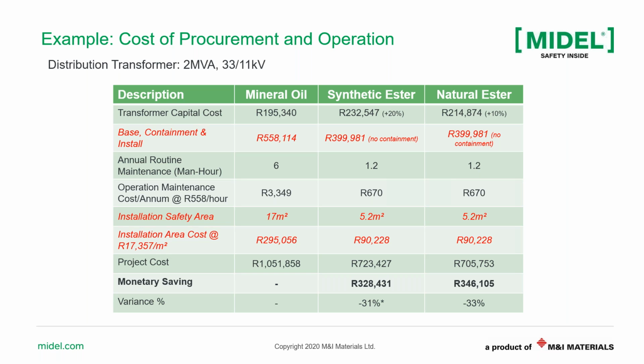But because esters are K-class and readily biodegradable, in the installation, you may not need containment. This is the second row there. So you have a reduction in the total cost of installation because you have reduced containment and footprint of the substation, and also in the total cost of the substation because the safety area is reduced. So with this example, we can see at the end of the project, compared to mineral oil, a synthetic ester can achieve lower cost by a third, minus 31, and natural ester is equivalent, minus 33.